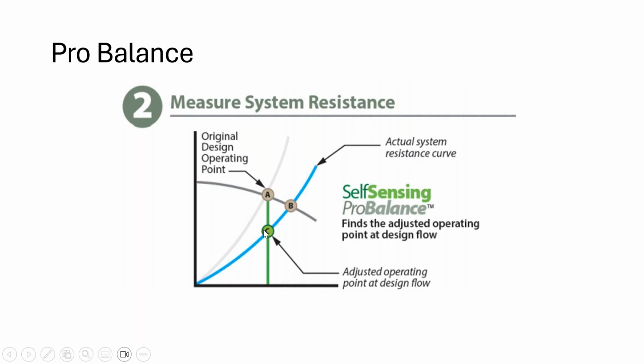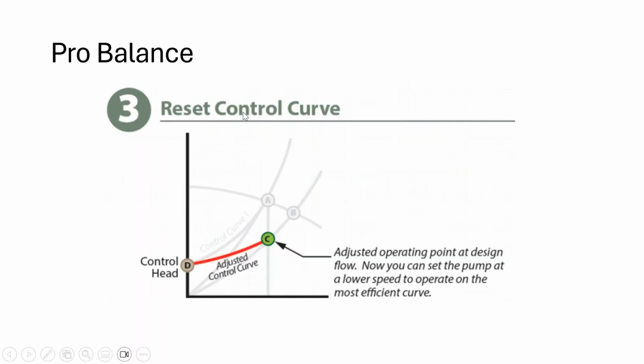And then you take it out of this mode, right? And you reset the control curve again with some keystrokes, so you're actually running on the adjusted control curve. It's kind of showing a little small curve here, but nonetheless, that is going to give it the most efficient operating point, and the system's going to be very, very happy in that regard.